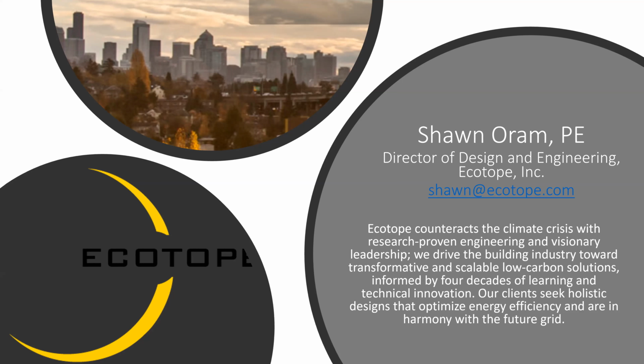The Advanced Water Heating Initiative has a retrofit group, a 120 volt and a 240 volt path. I'd imagine the retrofit approach on central heat pumps, which are in development, will follow a similar path where we have limited power availability. Also, the skid we showed is about equivalent in size to a single gas water heater, which shows the power of a half-inch gas line and how much energy is available there versus what we have to do using heat pumps. Space is also a major requirement. So retrofit is definitely the elephant in the room, and a lot of work is going to start going into getting off the ground with the tools needed and the basics.